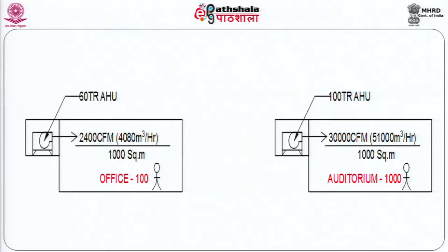Here is a comparison. If you have a 1000 square meter office, you will have in it maximum 100 people sitting at about 10 square meters per person. Comparatively, if you had an auditorium, you will seat instead of 100 people, 1000 people. The increased latent load of these 1000 people would reflect in the fact that the CFM here would be 30,000 and the CFM here would be 2400.